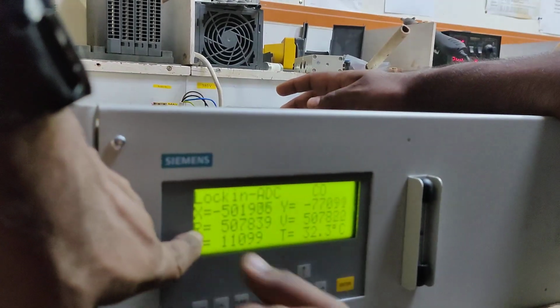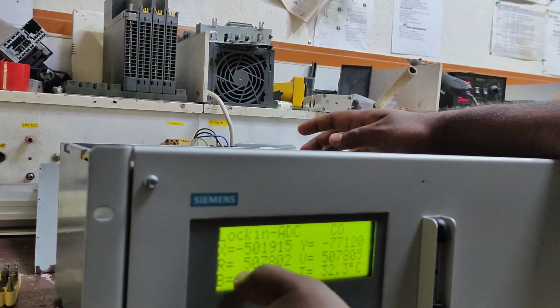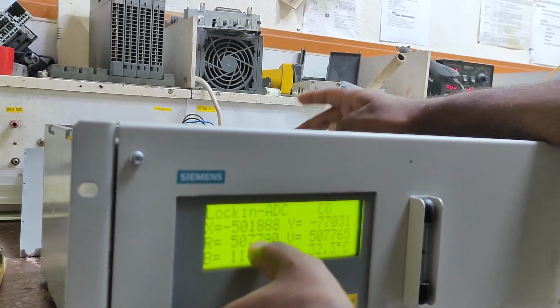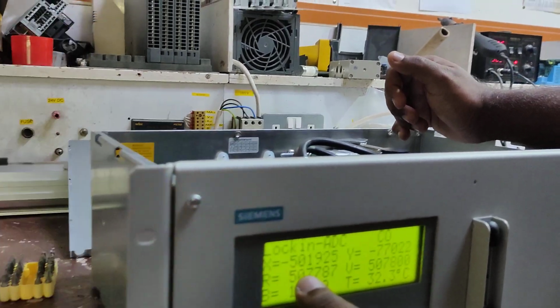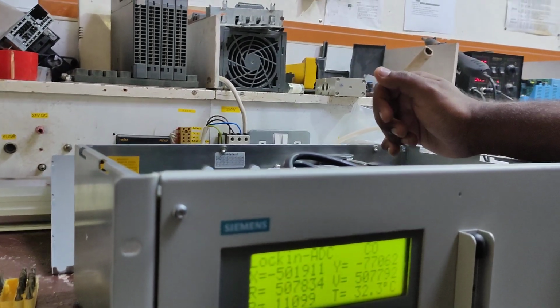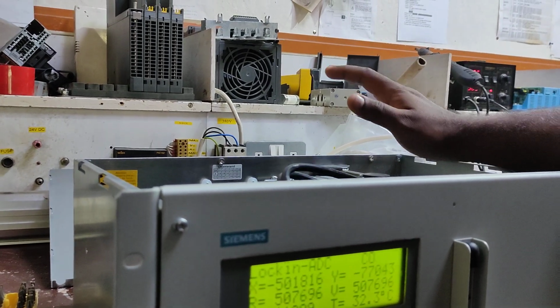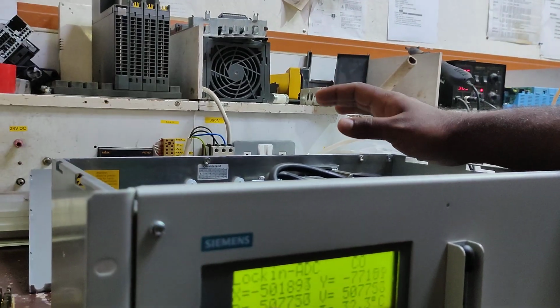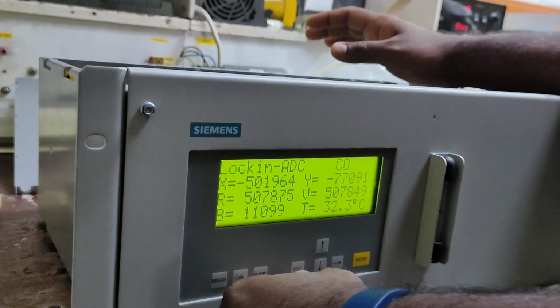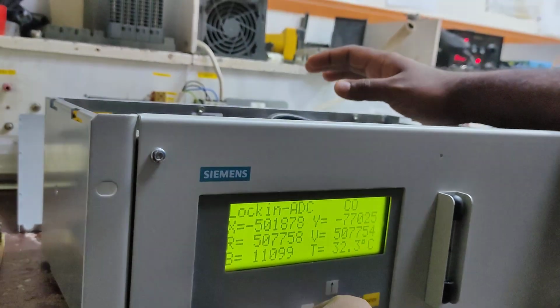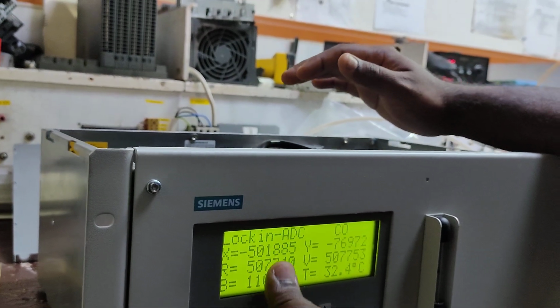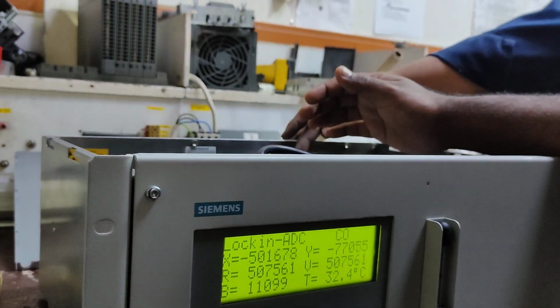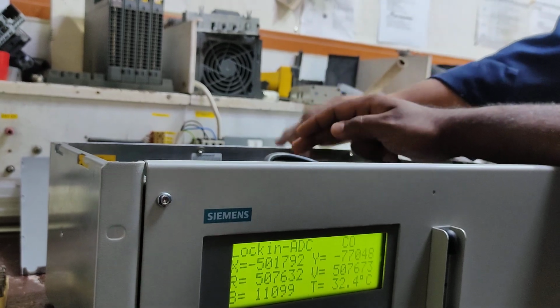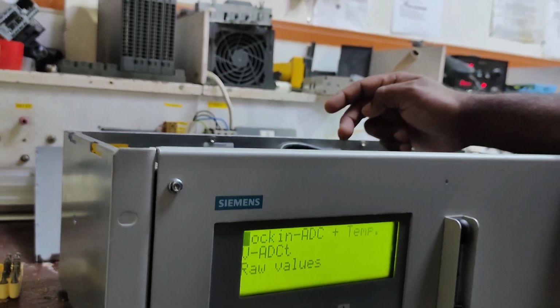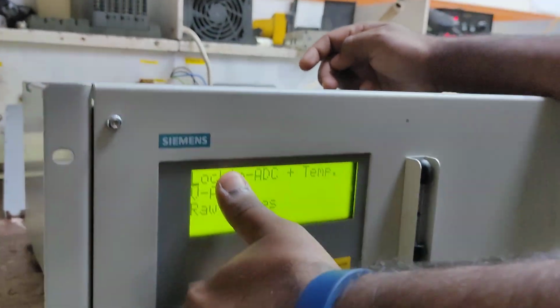R means resistance. This is a very important parameter. If you keep an eye on this parameter, you are keeping an eye on the detector. The minimum is 250,000. There is nothing like a maximum. This is a new detector, so you are measuring around 500,000, maybe 100,000 more. It will never go higher; it will only drop from here. If it comes down, replace this detector. So this is one parameter you have to focus on.